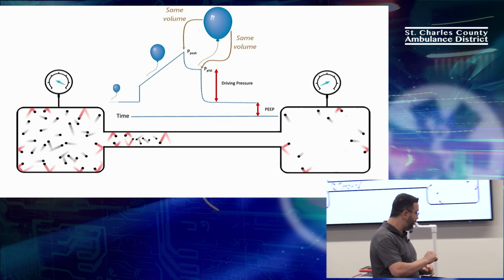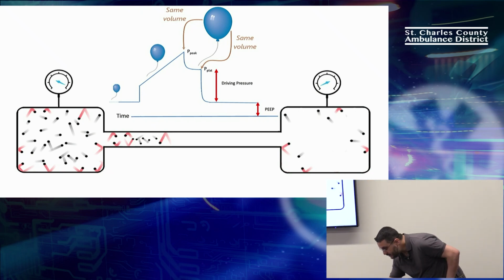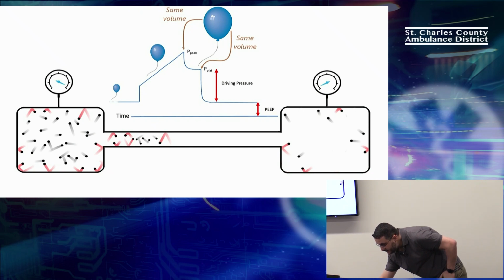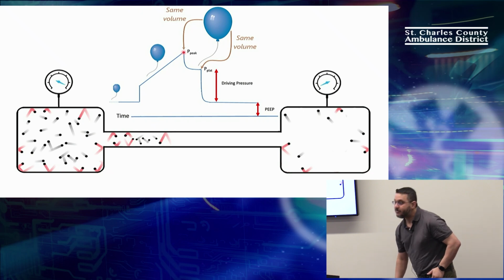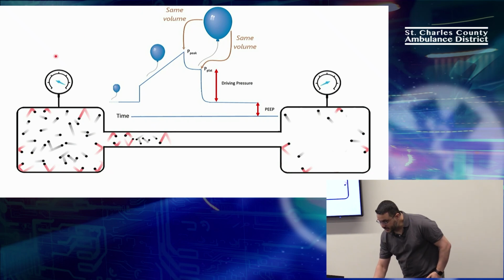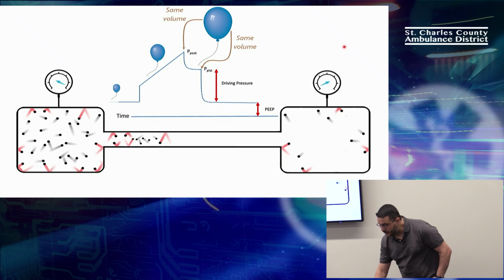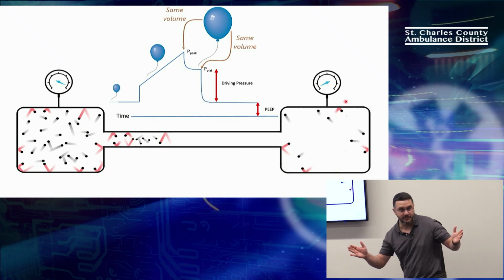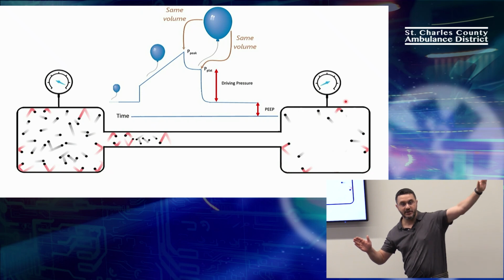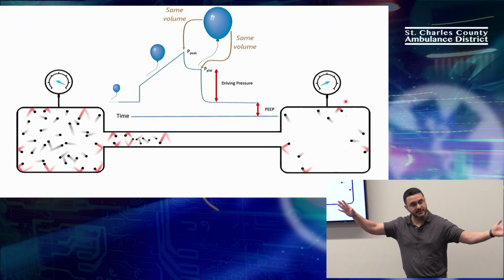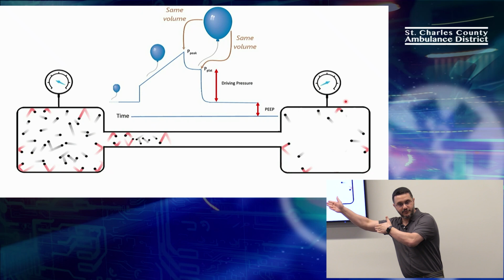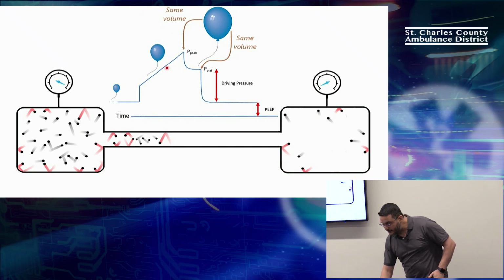The pressure is going to keep going up, and let's see if I can get a laser pointer here on this thing. So this is going to keep climbing up until something called the peak pressure. Now, the pressure on this side always has to be higher than the pressure on this side, or there will be no flow. Are you guys cool with that? The pressure on the ventilator side always has to be higher than in the lungs, or else air is not going to move.